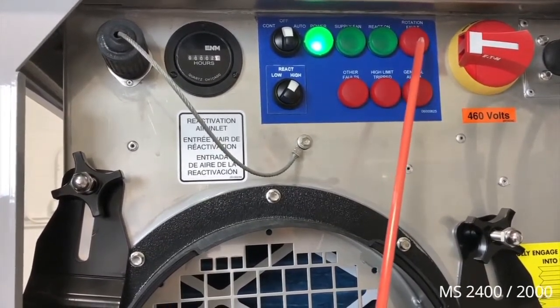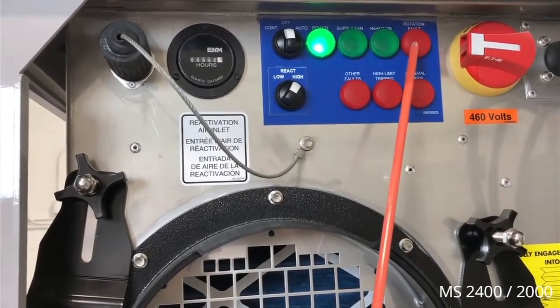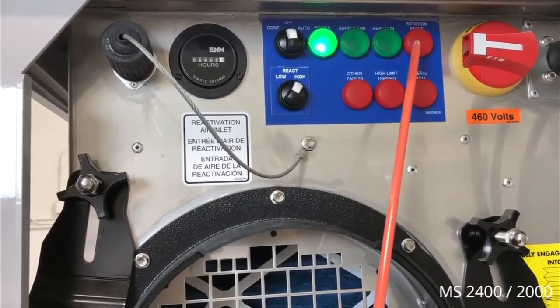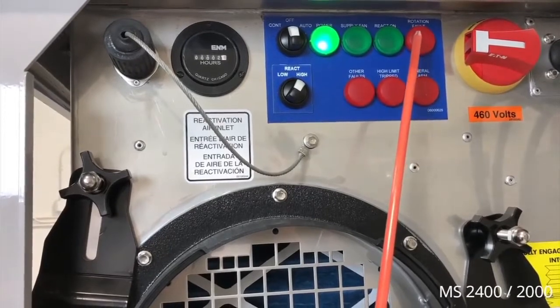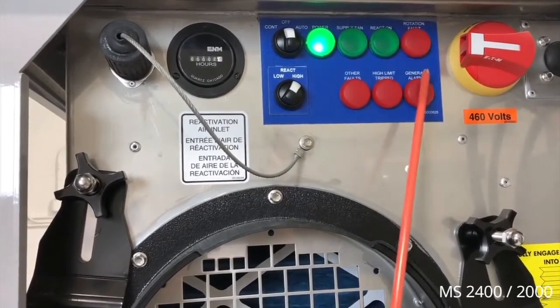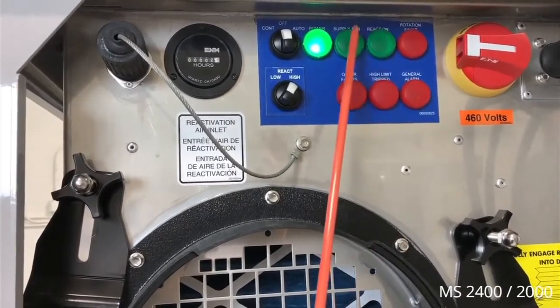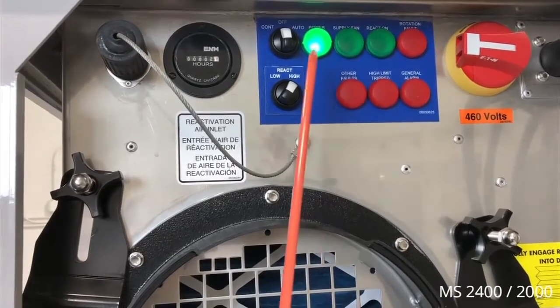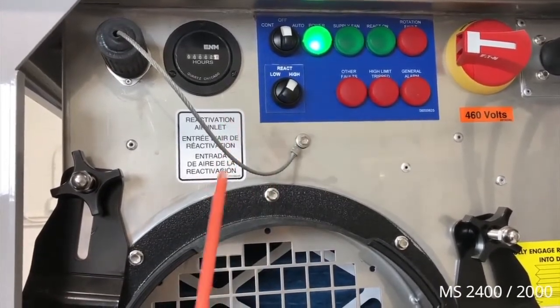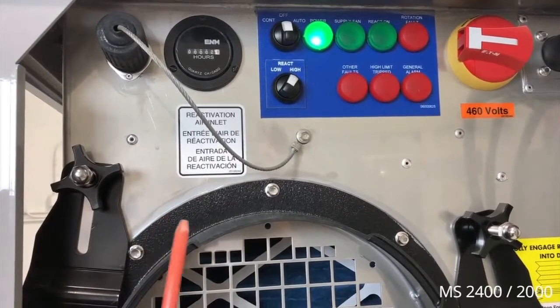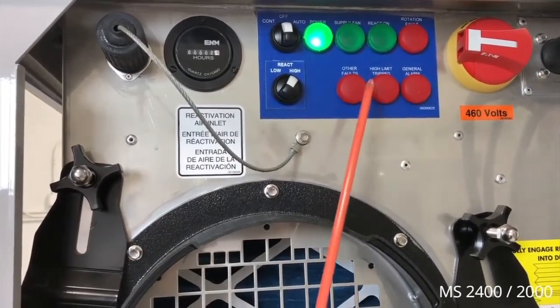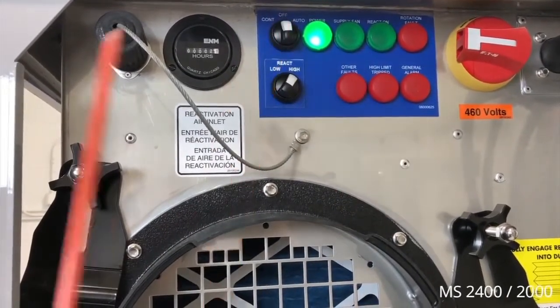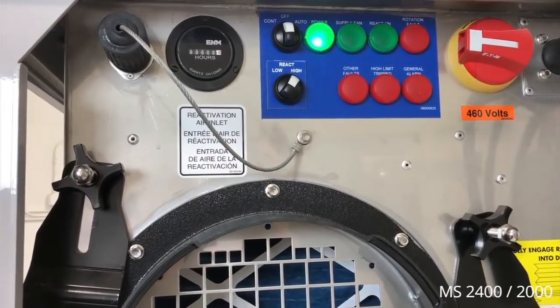The other alarm light is the rotation fault, and that indicates a problem if the desiccant wheel is not revolving. The other faults that can cause a general alarm are if these two blowers for some reason do not prove that they're operating with an airflow proving switch. That completes all the fault reporting. We're now ready to start the unit and watch it sequence through its operational cycle.